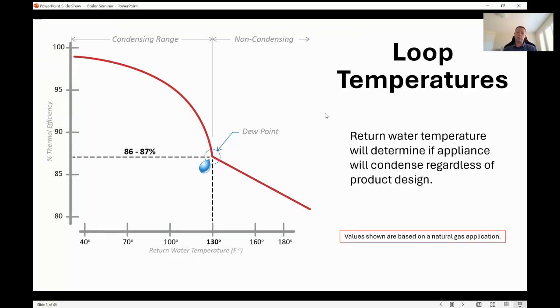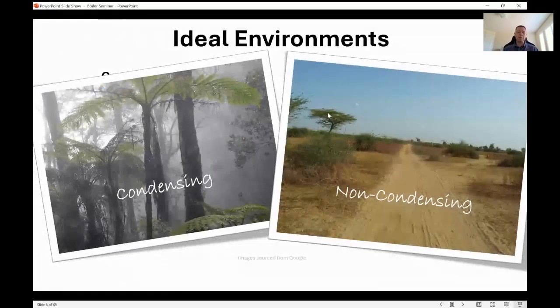You guys have probably heard of the term near condensing boiler, and a lot of those will have an efficiency of around 87%. They're non-condensing boilers. They need 130 degree return water temperature, but because that combustion efficiency is so efficient, that stack has the potential to have lower temperatures, especially when you modulate, and you'll generally need to have a condensing rated stack for it. So as I said, a condensing environment is obviously that one, like the rainforest. It's a very, very liquid environment, and a non-condensing environment will be like that desert, dry as dry can be.